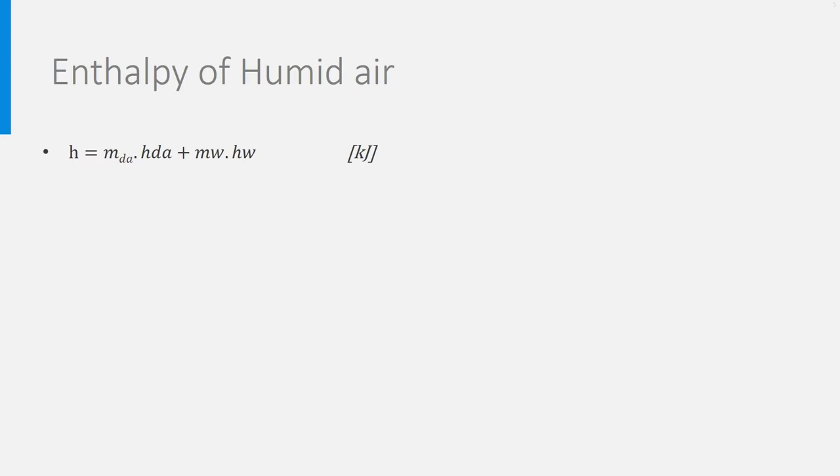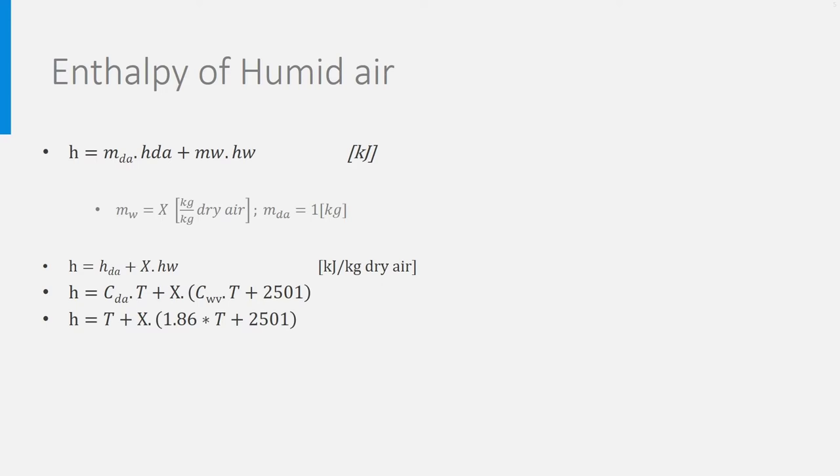Now that we know both enthalpies of dry air and water vapor, we can easily calculate the enthalpy of humid air. If the mass of water is Mw and the mass of dry air is Mda, then the enthalpy of the humid air is Mda times the enthalpy of dry air plus Mw times the enthalpy of water. We remember from other lectures that if we look at 1 kilogram of dry air, Mda is 1 and Mw is x, the absolute humidity, in kilogram per kilogram of dry air.